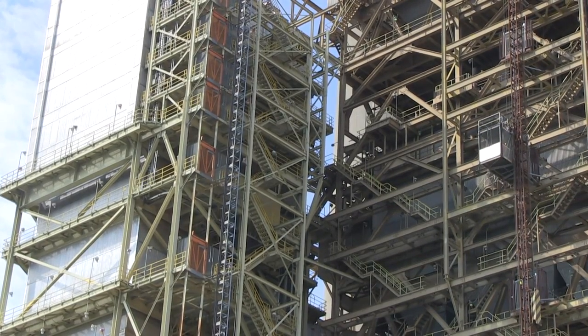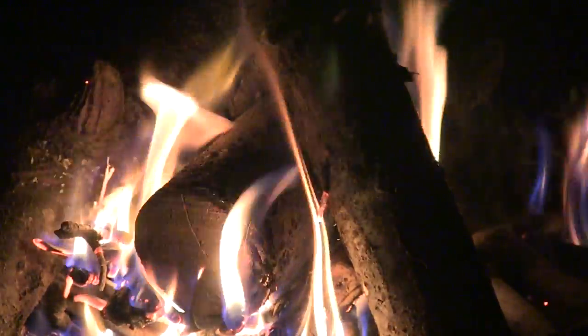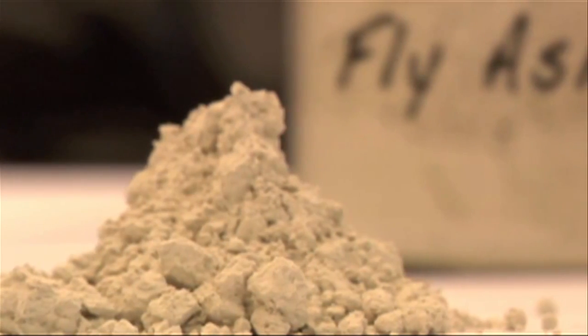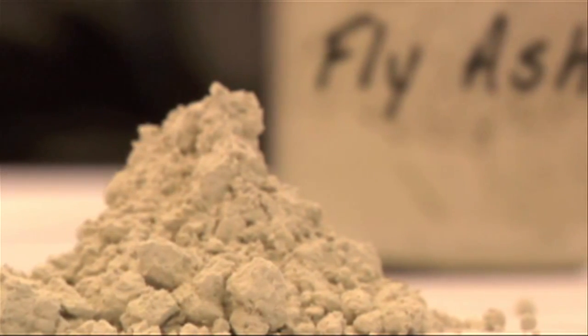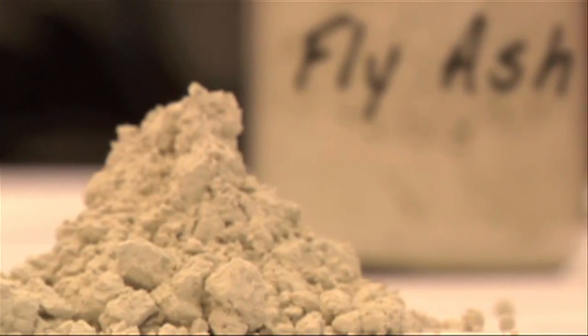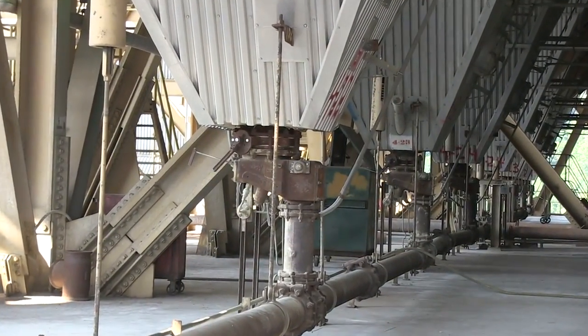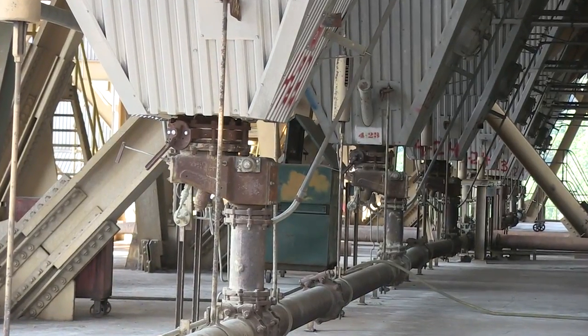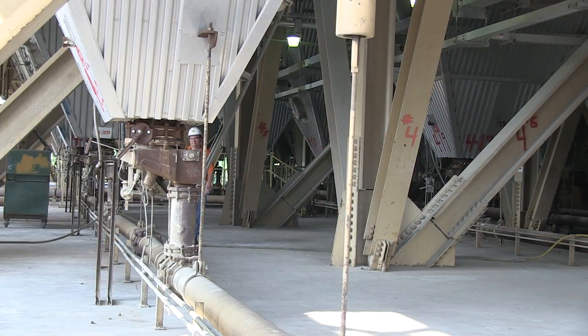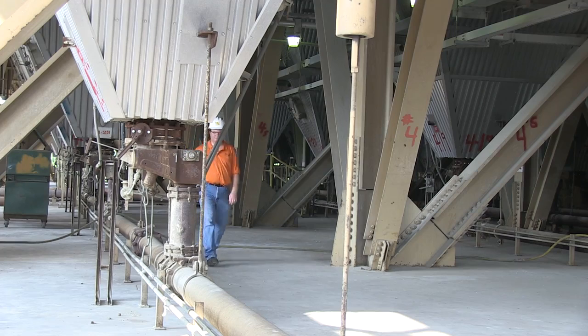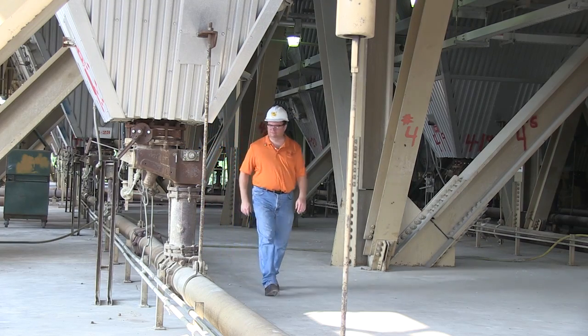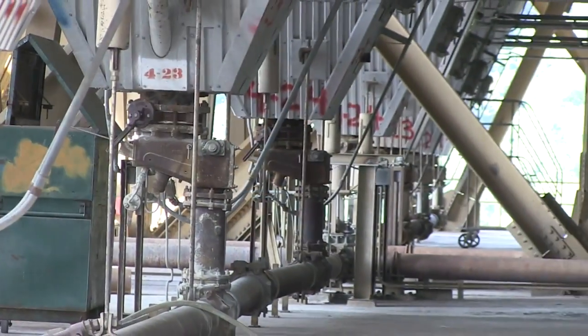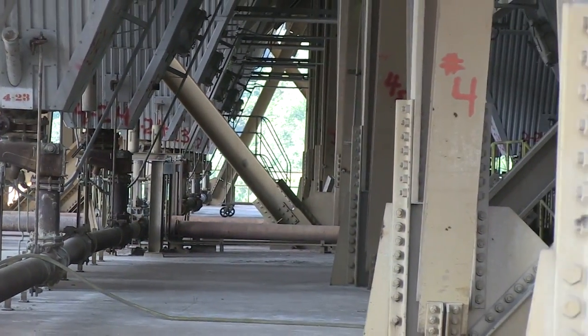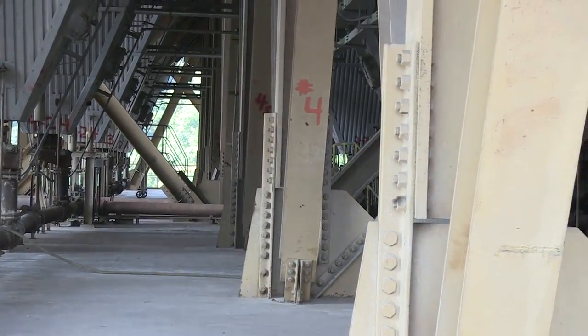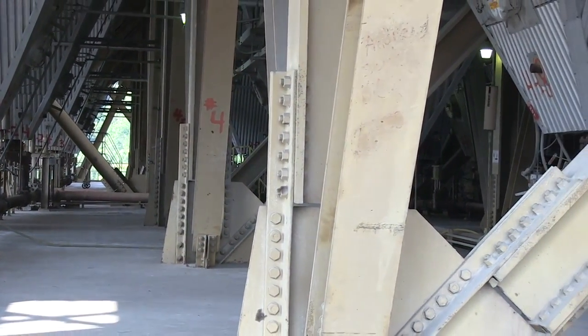It remains as particles of clay, rock, and minerals known as ash, similar to the ash left when you've built a campfire. About 80% of this non-burnable material is light enough to float out of the boiler along with hot gases. It's called fly ash. Electrostatic precipitators prevent fly ash from being discharged into the atmosphere, using electrically charged plates to attract and catch the ash. All 3 Cardinal units have precipitators, which remove more than 99.5% of the fly ash produced by burning coal. That translates to about 85 tons of ash per hour when all 3 units are running at full load.